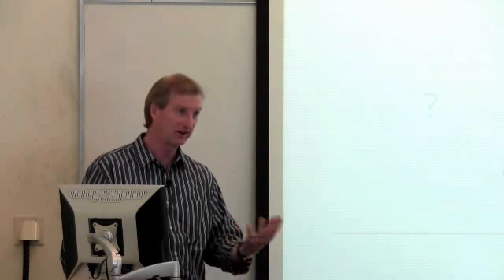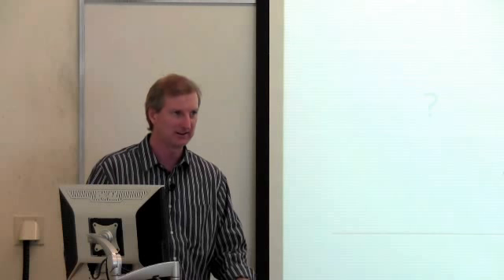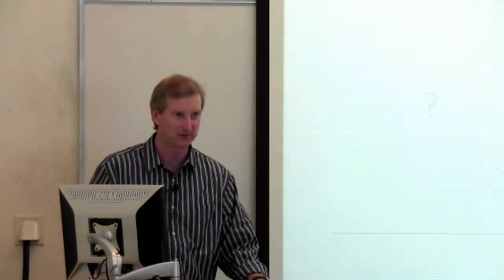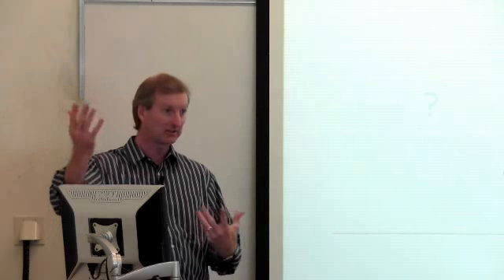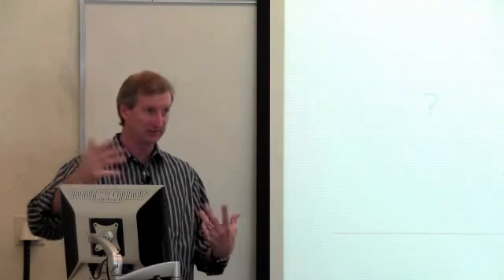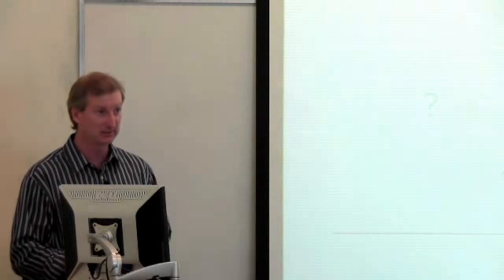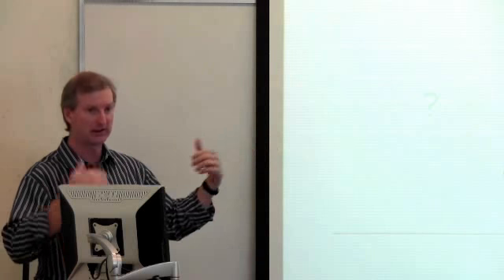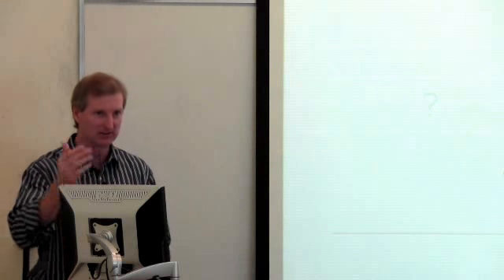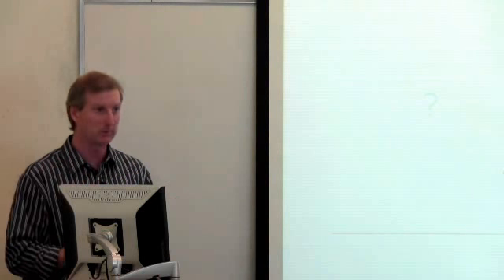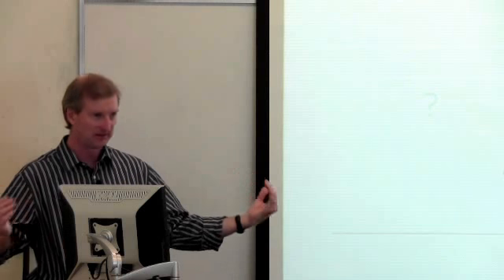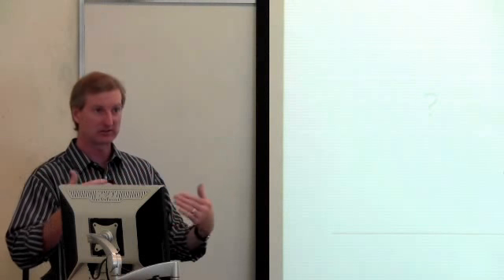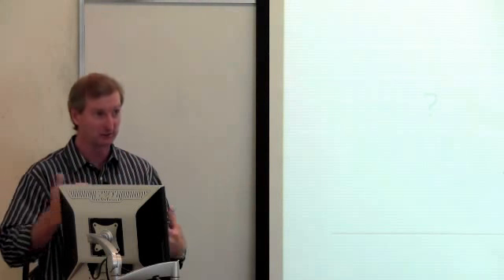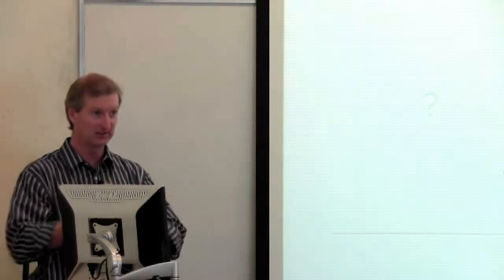So they are ECM motors, which are quite a bit more cost, but very efficient. So it's just, like I said, in the past, with looser built houses, you didn't need continuous ventilation. But as I was trying to show, under about 4 ACH, 3 and 2, especially under 2, you definitely need some balanced, what you would call balanced mechanical ventilation, where you bring as much supply in as is exhaust.